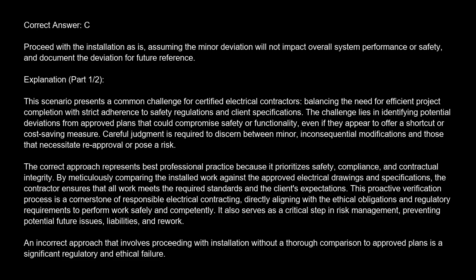The challenge lies in identifying potential deviations from approved plans that could compromise safety or functionality, even if they appear to offer a shortcut or cost-saving measure. Careful judgment is required to discern between minor, inconsequential modifications and those that necessitate reapproval or pose a risk. The correct approach represents best professional practice because it prioritizes safety, compliance, and contractual integrity. By meticulously comparing the installed work against the approved electrical drawings and specifications, the contractor ensures that all work meets the required standards and the client's expectations.